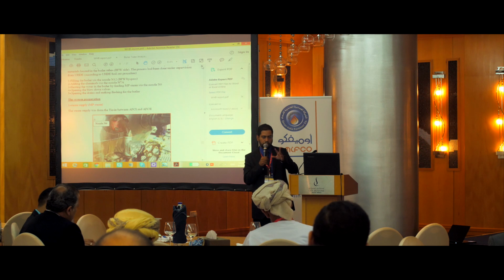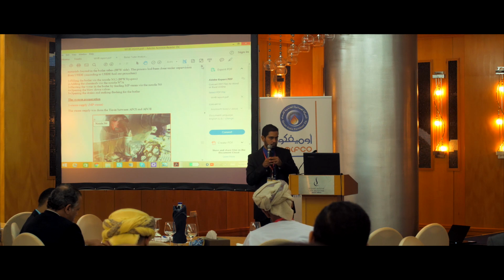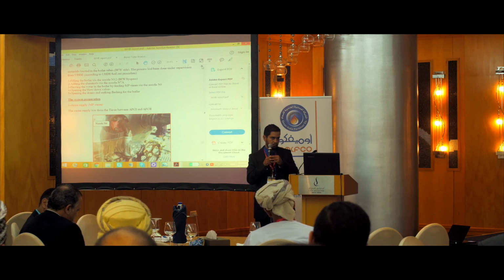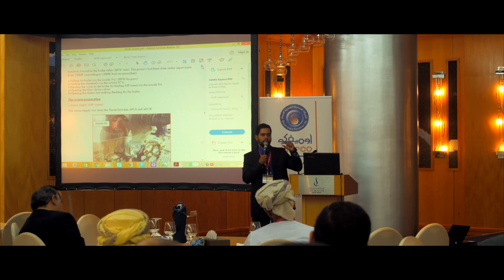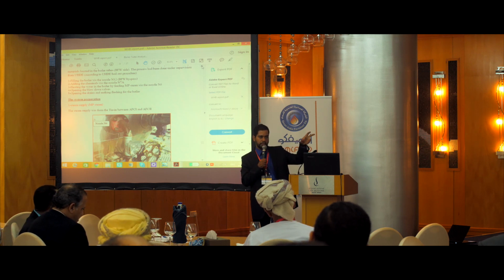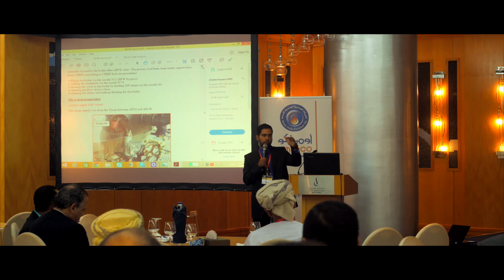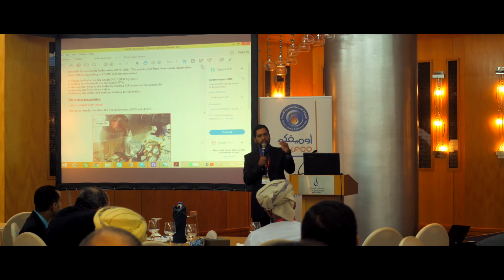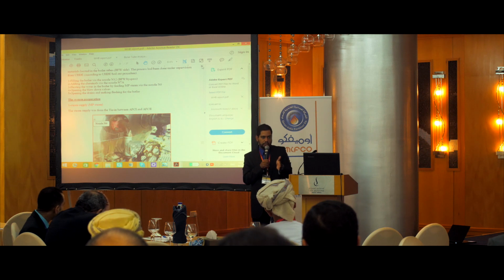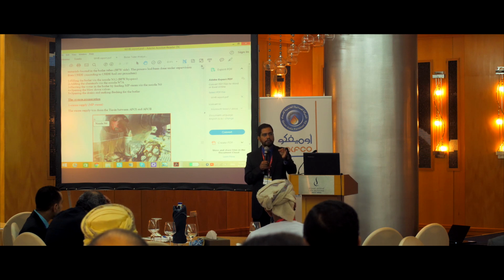At the same time, when the failure happened, there is no reference for the failure shape in the waste heat boiler because we plugged the tubes. There is no indication, or we didn't do a destructive test for that. But the evidence was in the tubes of the main boiler, not the waste heat boiler.